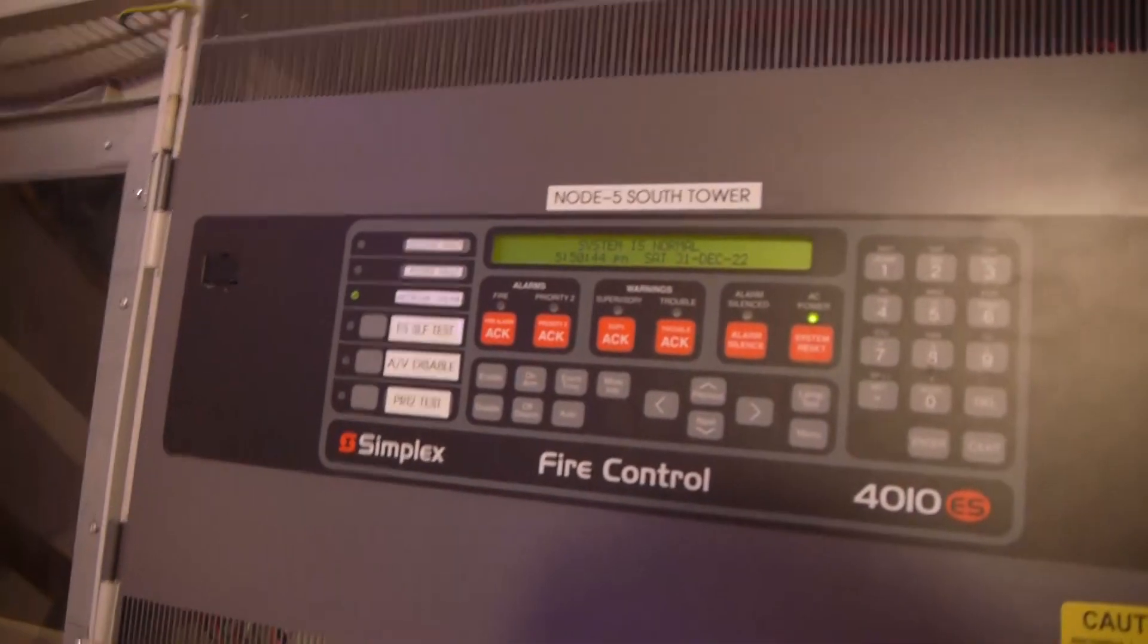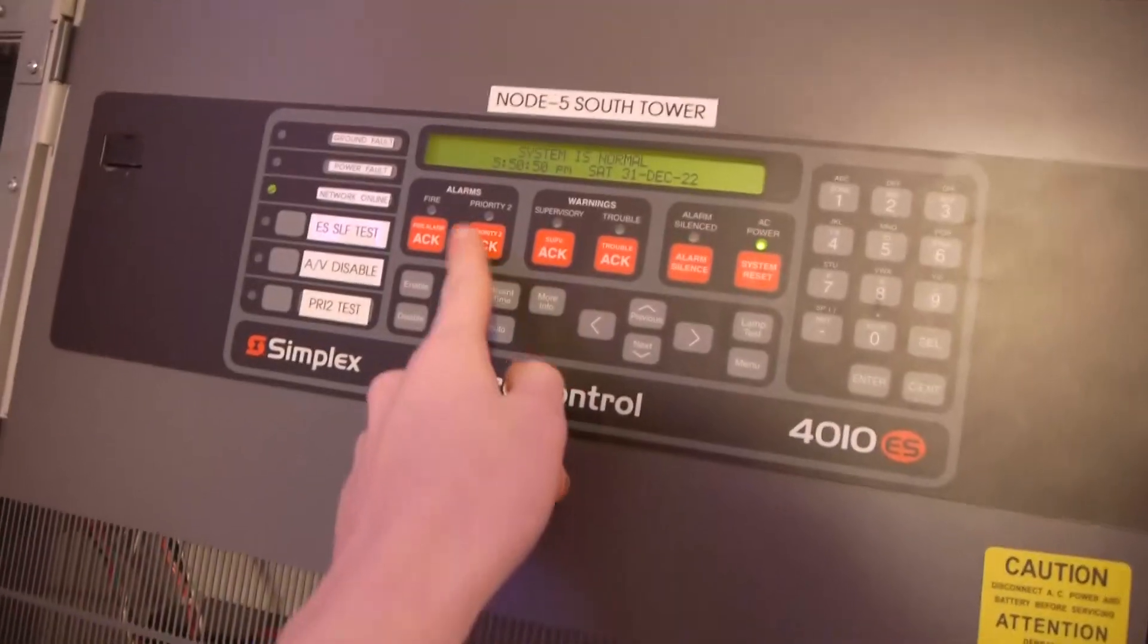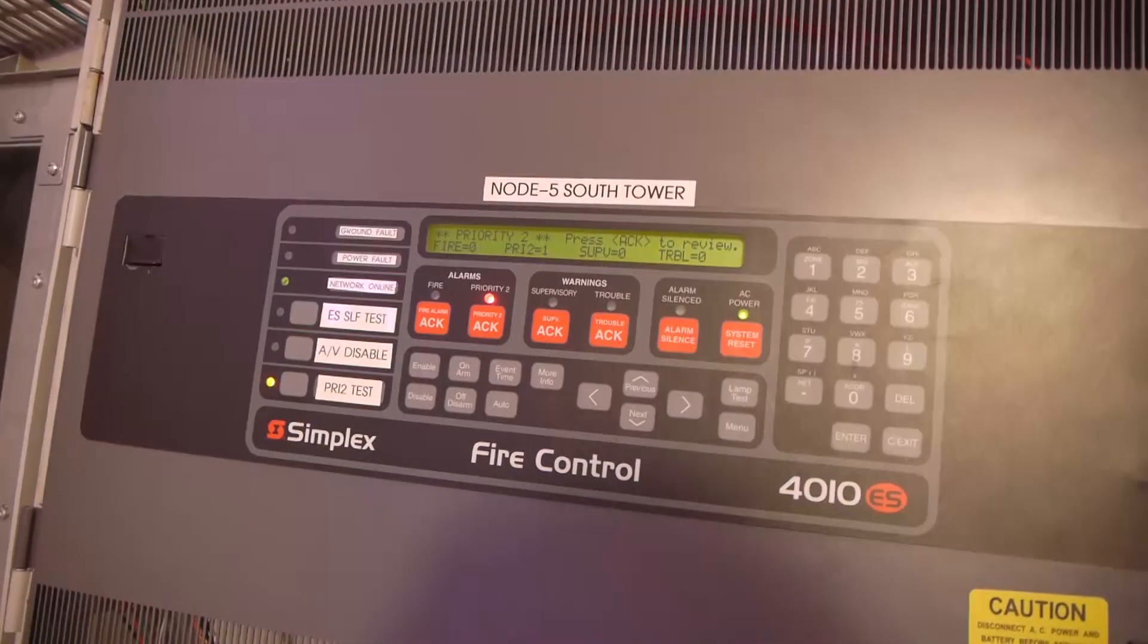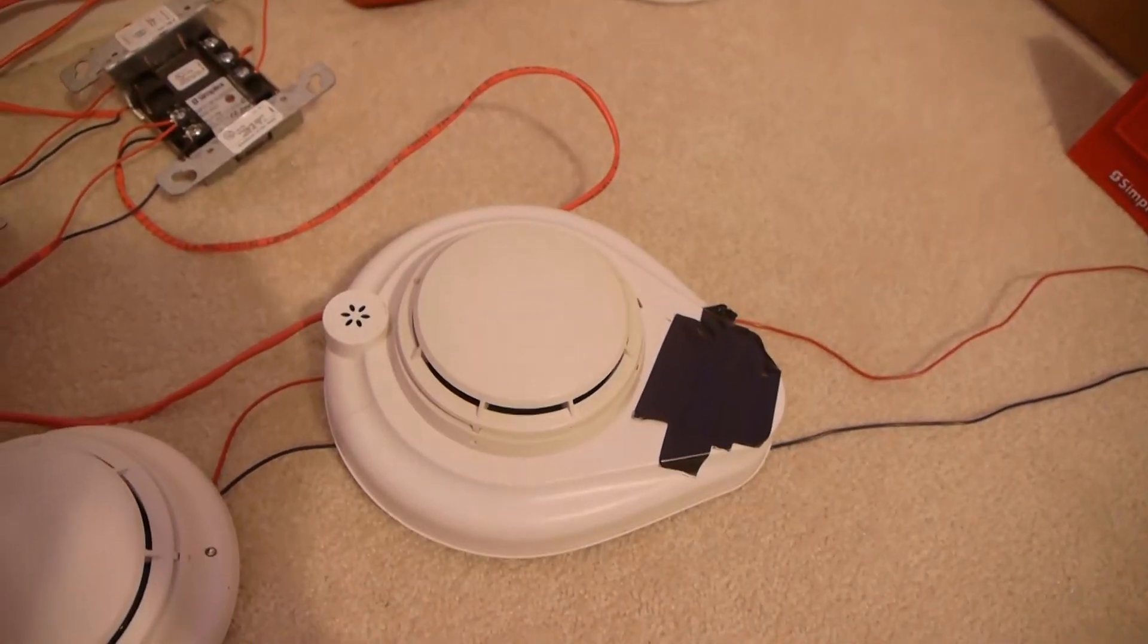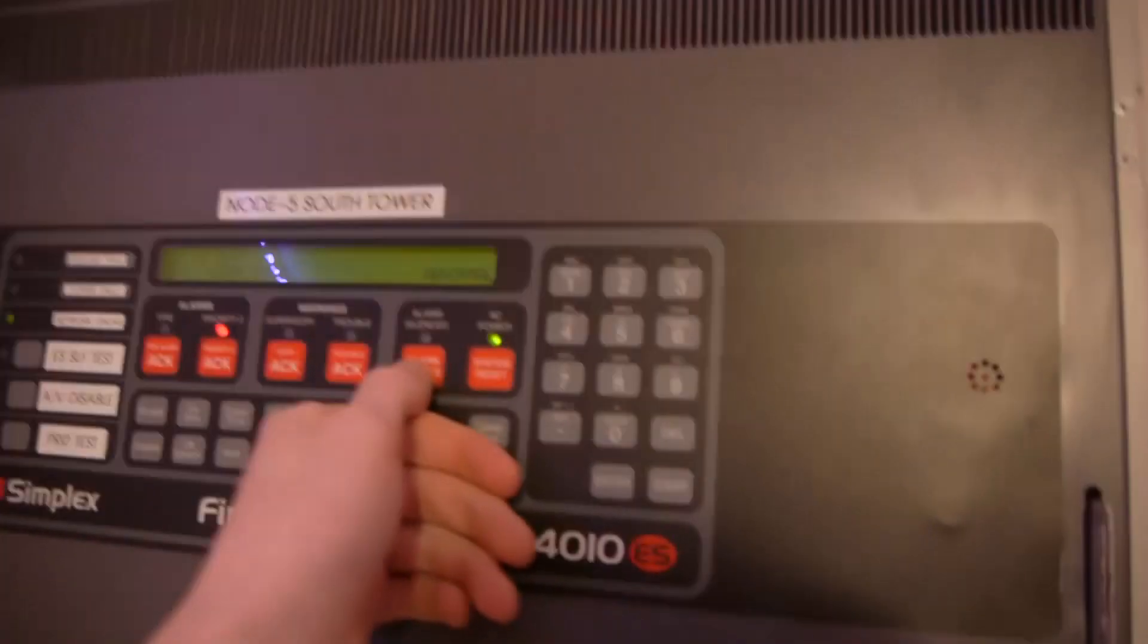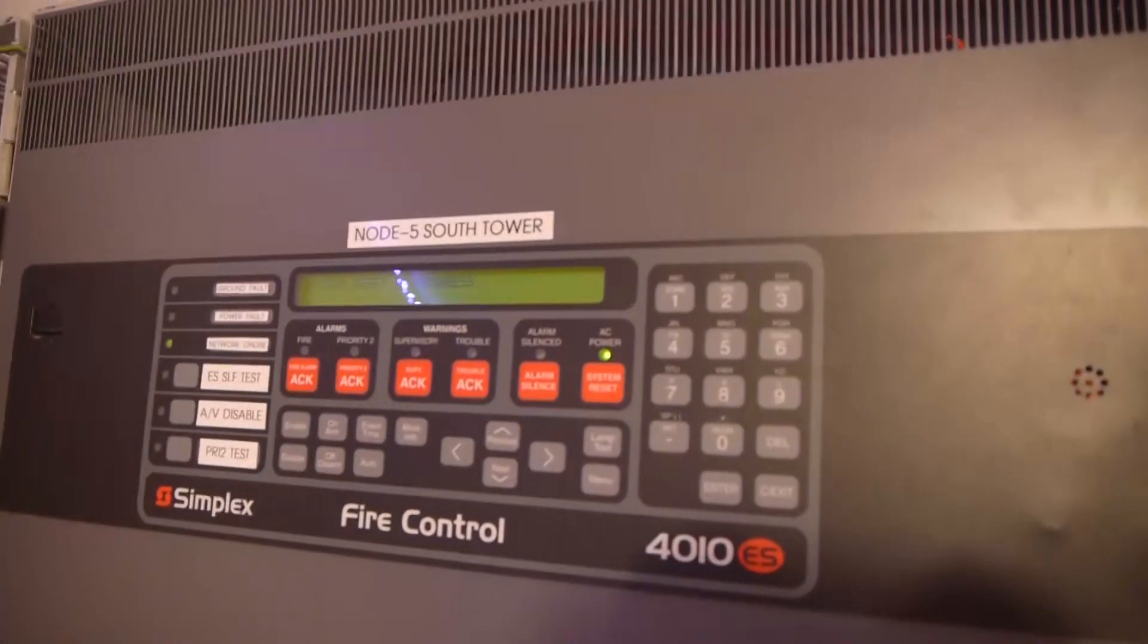So first of all, we can go ahead and test the carbon monoxide setup. So I have it set to priority 2, you could also set to supervisory if you wanted to, but since this has priority 2, I set to priority 2. So this is basically simulating the carbon monoxide on the detector going off. You can see we have an event come in here, so we can acknowledge it. And you can hear it's doing code 4. And you can see this relay module right here is on, and the one on the panel is on, basically making this module do the coding. So you can go ahead and hit silence, which I programmed. It doesn't actually make the silence light go on, but you can see it turned off this relay. And the relay inside the panel, basically cutting power to this base. And we can go ahead and reset, which will automatically turn off the point and everything. And that's all done via custom control, normally the panel does not do any of that automatically.